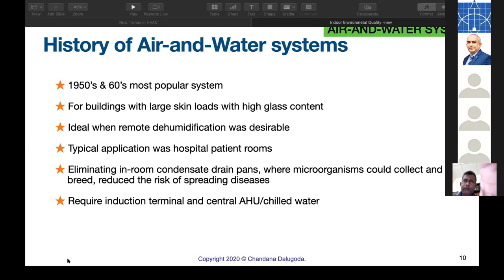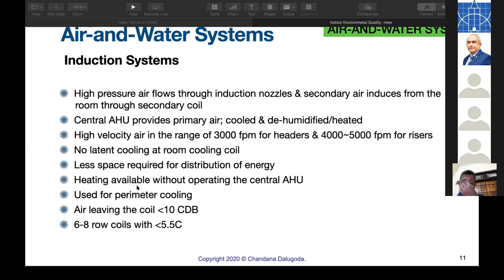But then suddenly, a decade ago, this came back in full force. Now, these systems fall into chilled beams, and in these particular induction systems, all came back to life because of the energy conservation need. Now, a few details are here on induction systems. I'm not going to go through all that. You can refer later. Now, one thing, the air leaving the coil in the main AHU is 10 degrees C. And mind you, a low chilled water temperature is also required. Especially the air leaving will have a lower moisture content. In turn, that can absorb moisture in the air in the room.